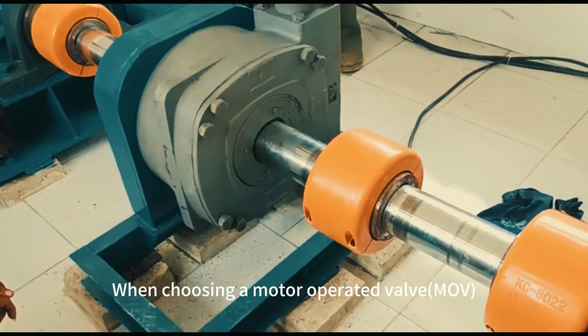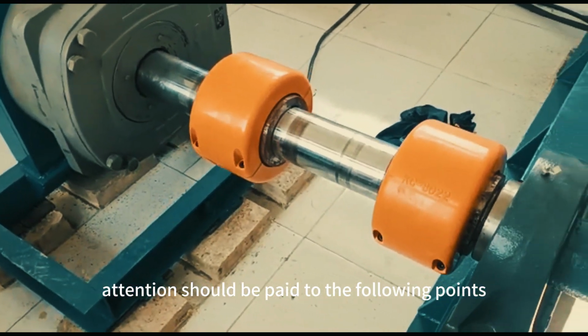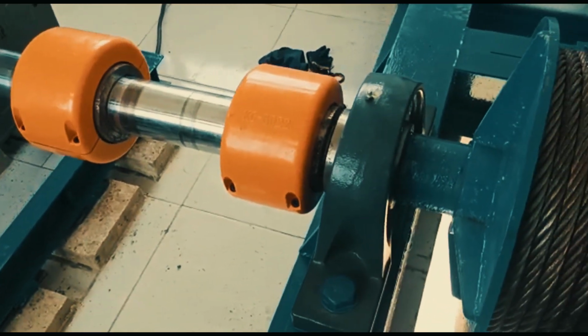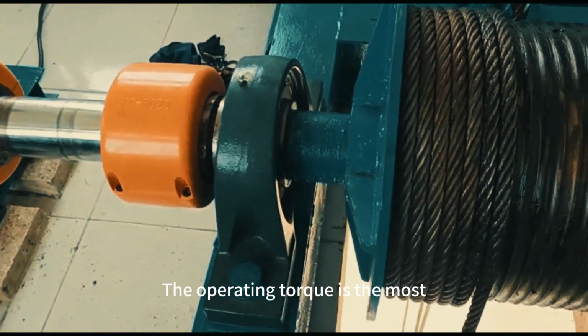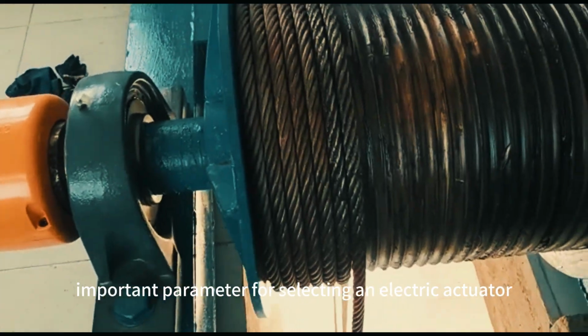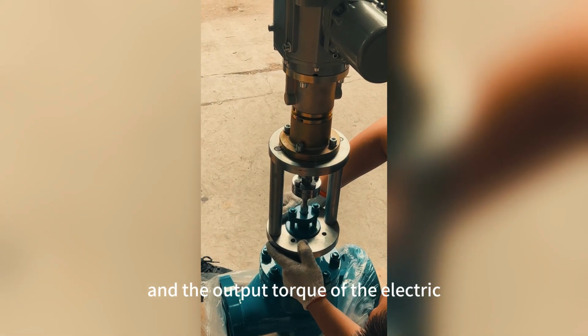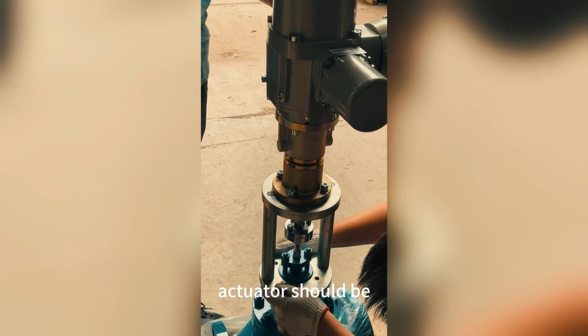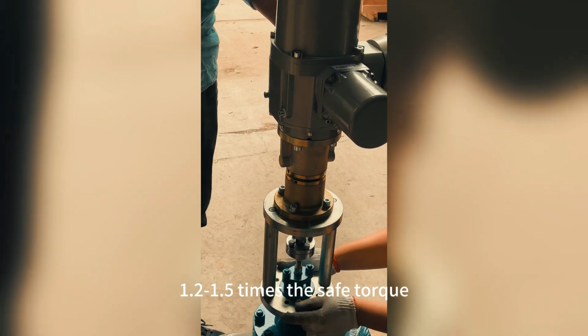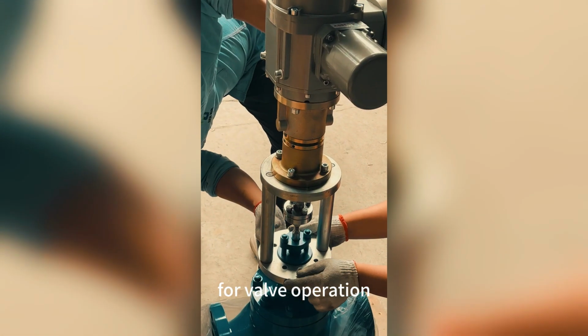When choosing a motor-operated valve, attention should be paid to the following points. The operating torque is the most important parameter for selecting an electric actuator, and the output torque of the electric actuator should be 1.2 to 1.5 times the safe torque for valve operation.